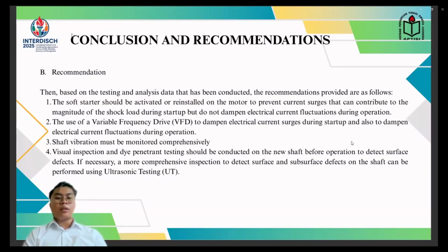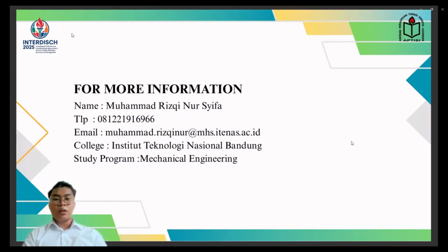Visual inspection and penetrant testing should be conducted on the new shaft before operation to detect surface defects. A more comprehensive inspection to detect surface and subsurface defects on the shaft can be performed using ultrasonic testing. This is for more information.